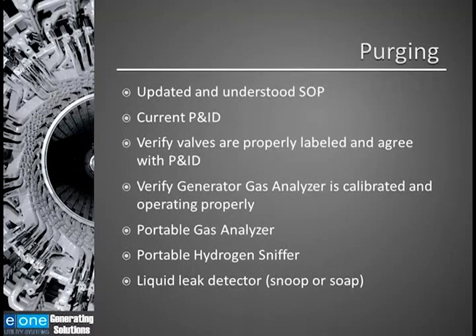Because of recent events in the U.S., I'd like to spend a little time discussing purging a generator, or degassing or gassing a generator. When proper operating procedures are followed and the operation is performed by experienced plant personnel, there will be no issues. However, this is not always the case, especially with us getting a younger workforce at power plants. You need updated and understood standard operating procedures. This is critical. The first two items are critical.